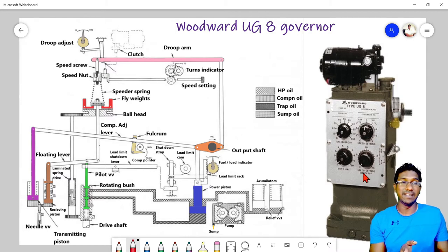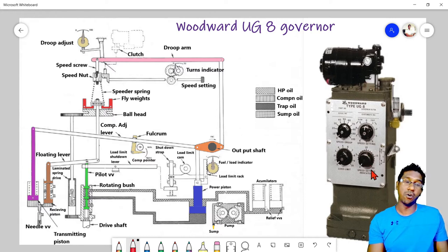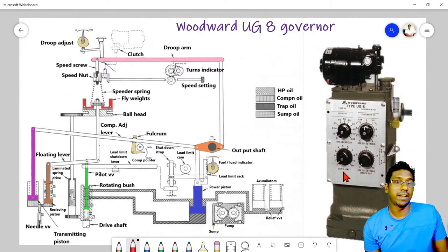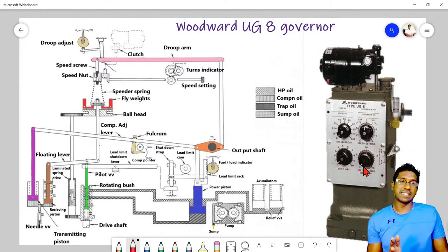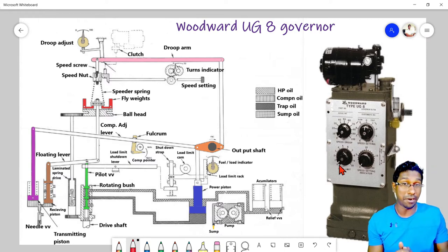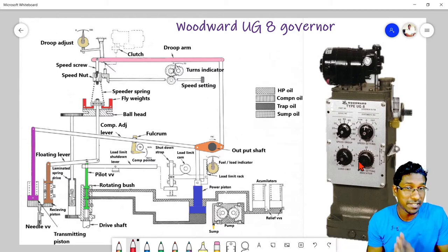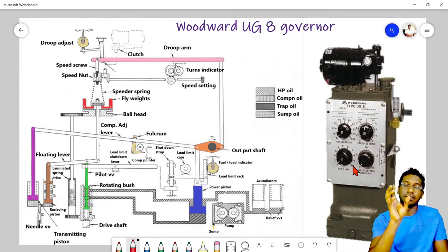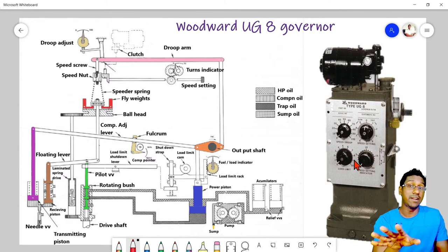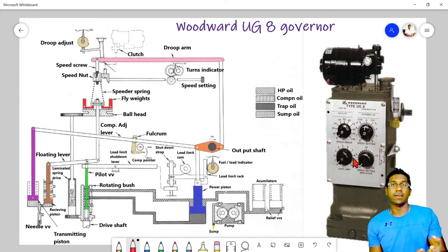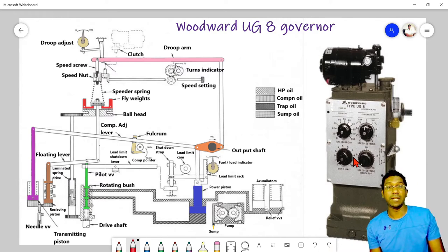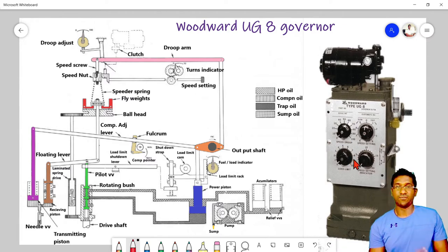The turns indicator is a speed setting indicator that simply counts how many turns have been made on the speed setting — it has no other special purpose. The third dial is the load limit. Setting it to zero means the fuel rack will remain at zero and the engine will not run. Setting it to 10 gives 100 percent load — for a 1000 kW generator you would put it to 10 for full output. If you want to cap the load at 80 percent, set it to 8 and the governor will limit maximum fuel to that 80 percent.